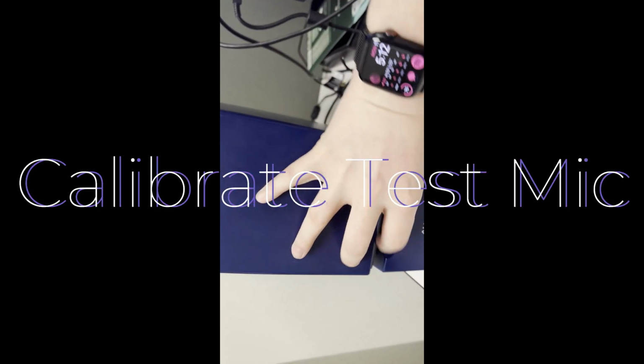Okay, so the next thing we have to do is calibrate the reference test microphone. So you can see here, we've got that 1 to 2 millimeters in front of the reference microphone. Over here in Oto Suite, we clicked on Navigator, we clicked Standard Tests under Hit. We went up, we clicked Tools, and then we clicked Aurical HIT Calibration, and then we clicked Reference Test Mic Calibration, and now we're gonna hit Start. All right, and then we click finish, and that is how you calibrate the reference test mic.